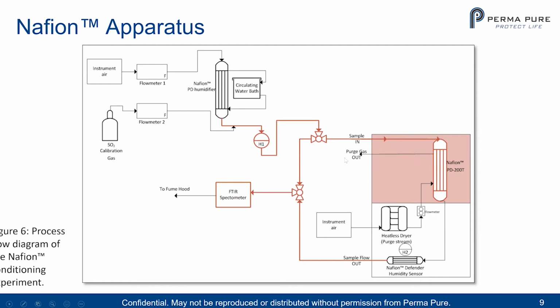So let's look at our Nafion apparatus here. You can see we have on the top the humidification of the calibration gas. That goes into our sample in here. That goes into our dryer, and then from our dryer we have our Defender humidity sensor to detect the humidity coming out of the Nafion dryer, and then from there we go into our FTIR spectrometer. So we're able to do a before and after.